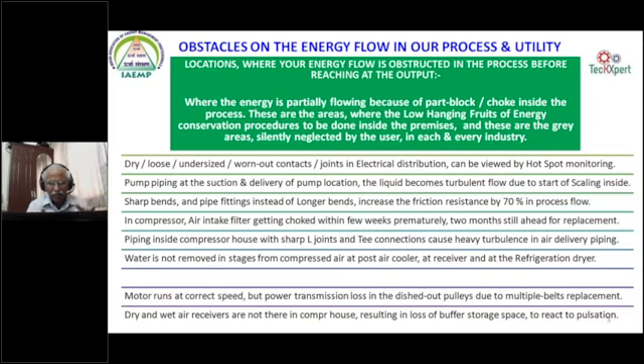So these are all the areas on the electrical side, after the motor, whatever we are receiving from the transformer at 415 volt plus or minus 5 volt, when it reaches the motor, it is plus or minus 10 volt or 20 volt or 30 volt. The more and more the unbalance in voltage, the motors get derated. At almost a 5% unbalance on a given three-phase motor, the derating goes almost to 25%. So the corrosion of contacts, especially the dry or loose or undersized or worn out contacts, these are all the areas on the electrical distribution side.